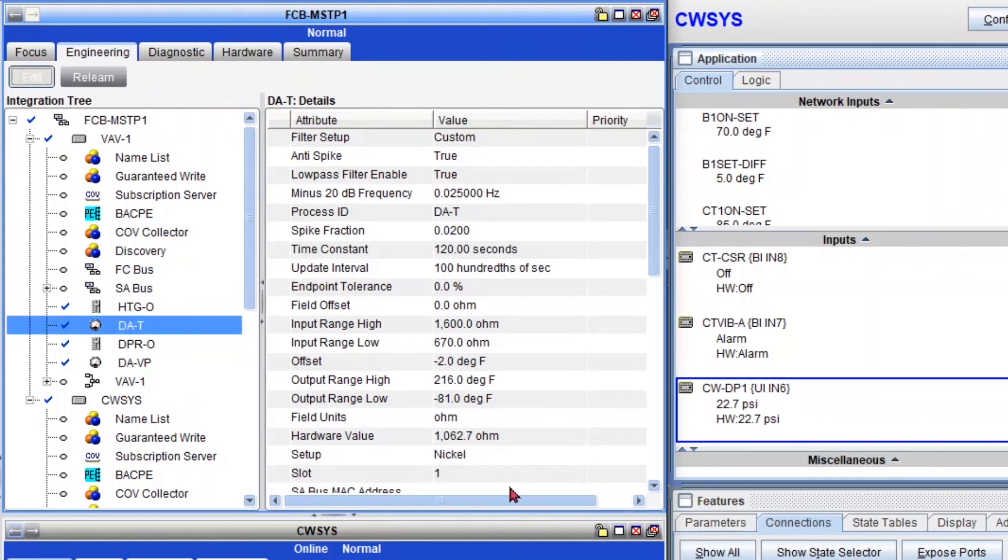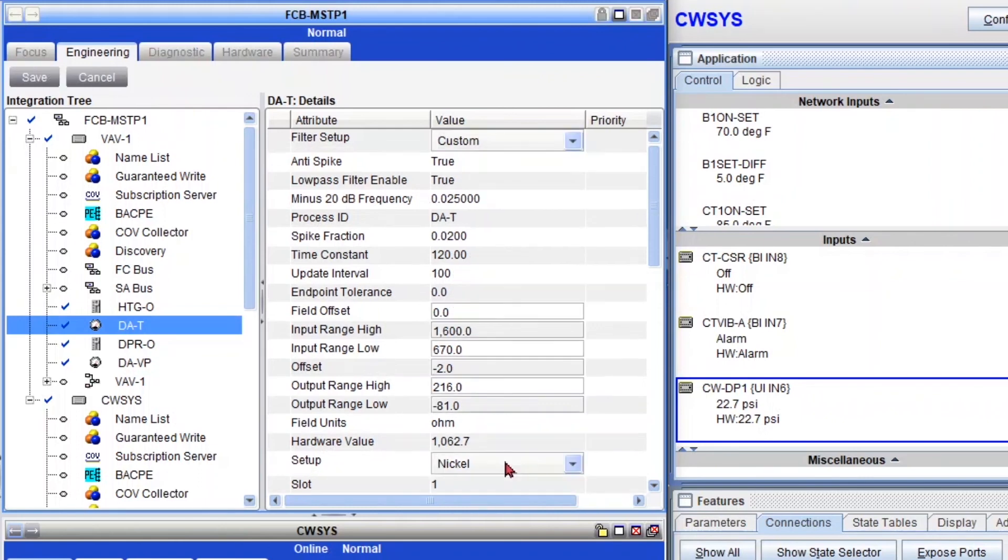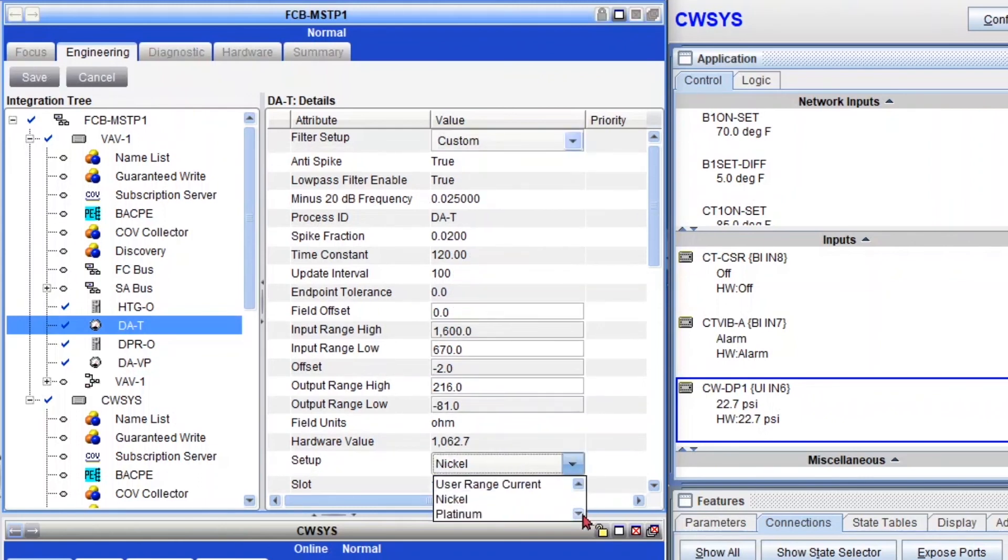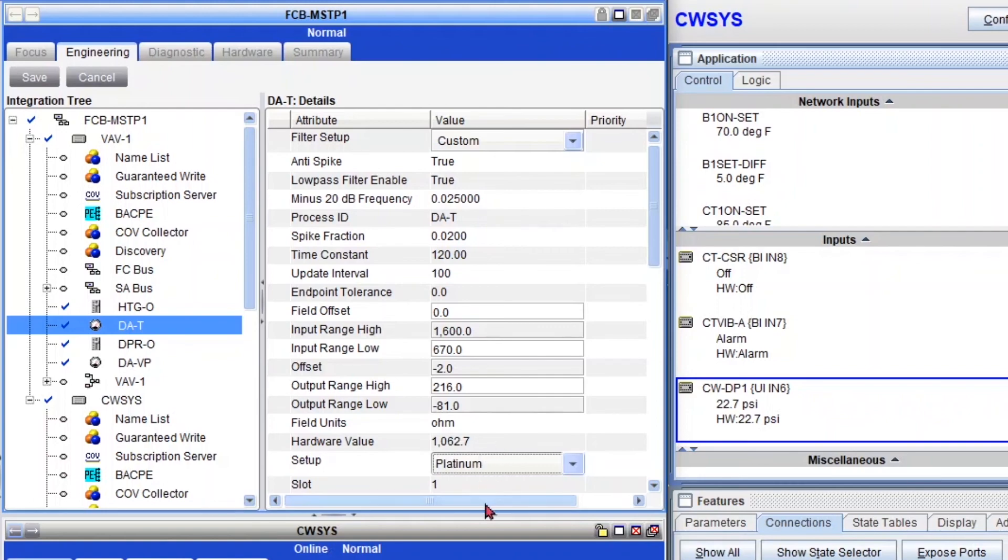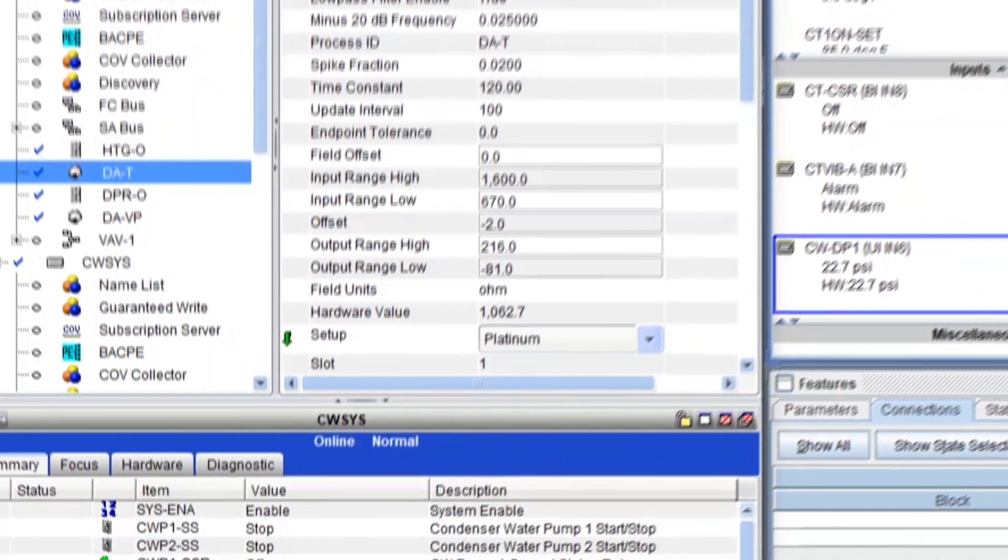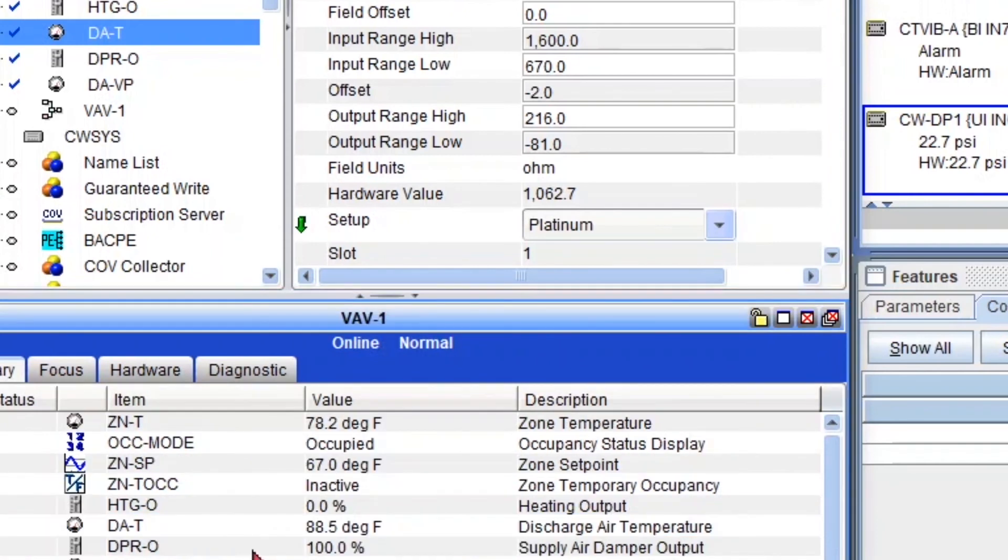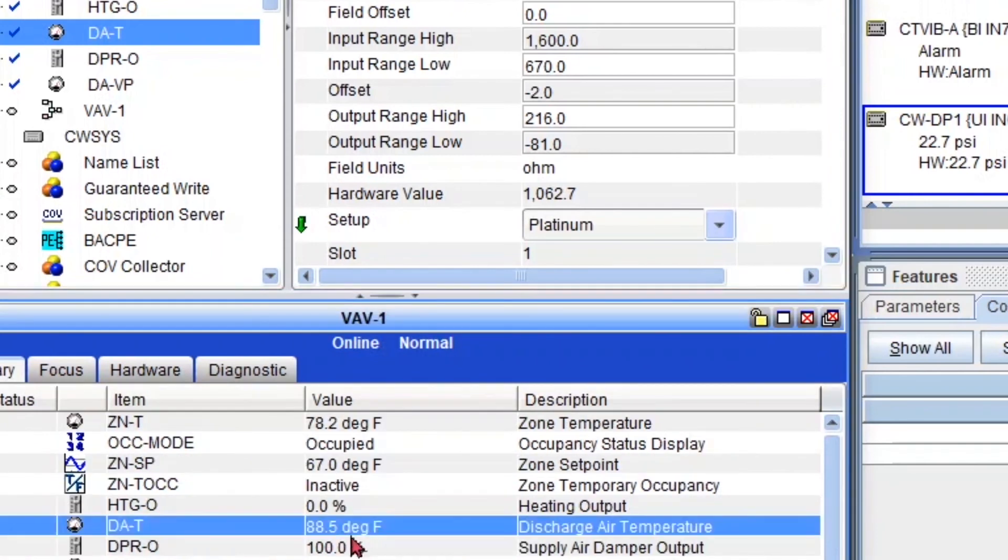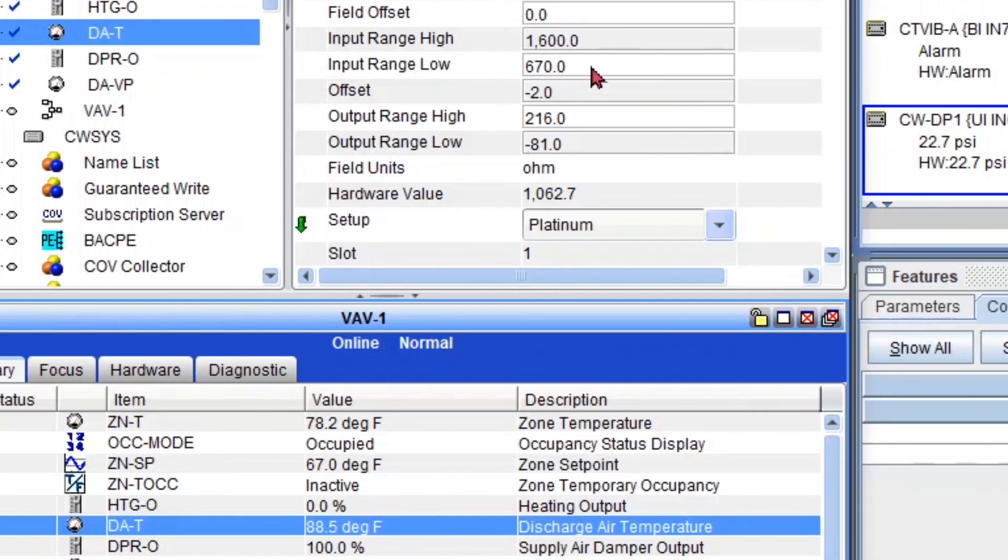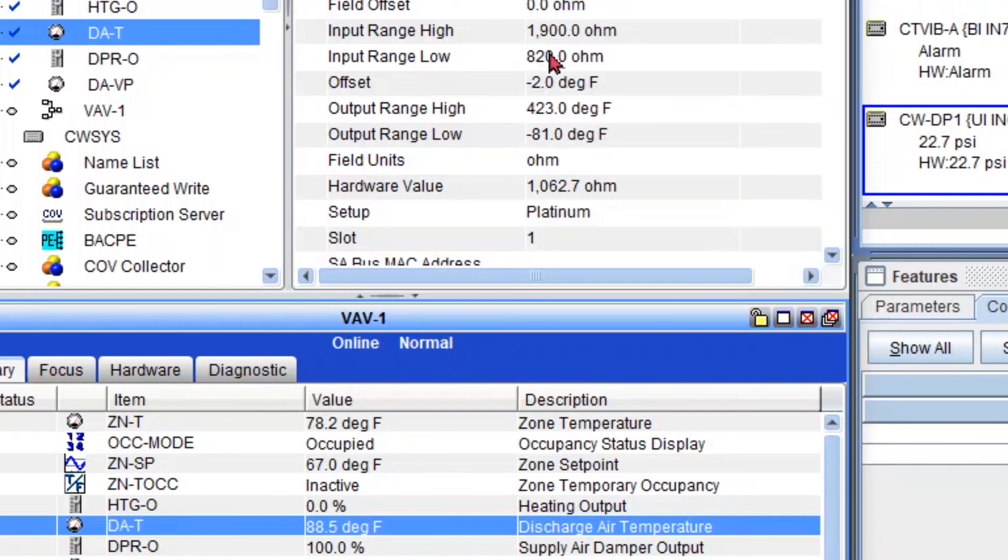And if you save the settings, you will also see the changes. I can show you really quick. So right now we're reading 88, so I'm going to save it. And it's also going to automatically update your ranges from 1600 and 670 to the actual platinum settings. These are in ohms, 1900 and 820, and you'll see that my sensor changed.